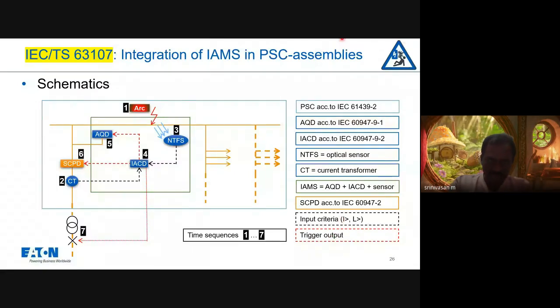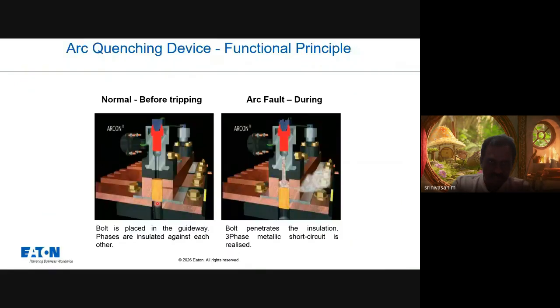If you look at both pictures, you could see there is one insulator plate. Before the Arcon is actuated, we make the bolted short already. Before the Arcon is actuated, there is an insulation plate, so the short circuit will not happen. Once the Arcon is actuated, this insulation plate will break, and it makes the continuity of the short circuit.